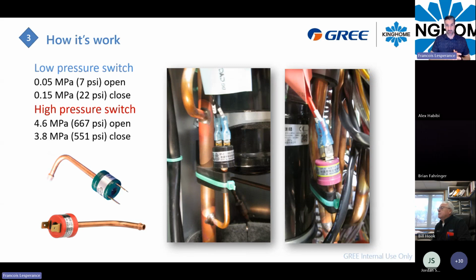Also, the system is equipped with a low pressure switch and a high pressure switch. Those switches are for protection only. If you have an issue with the system and you hit 667 psi because something's blocked, the high pressure switch will open and shut off the system. You will have an error code related to that. Same thing for the low pressure switch: if you have a leak and you have less than 7 psi inside the unit, the low pressure switch will open and you will have an error code related to this.